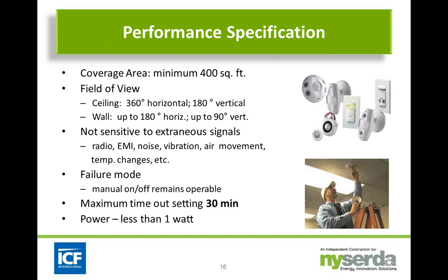Failure mode. Especially with the wall-mounted switches, you want them to fail to the on position as long as the off remains operable. This matters for ceiling-mounted sensors, where you can't reach them very often. If you can turn the devices off, turn the switches off. Maximum timeout setting shouldn't be any longer than 30 minutes, and this is actually dictated by the ASHRAE codes or standards. And then this last item, you want to be careful to specify the standby power. You want to make sure that it's less than 1 watt.